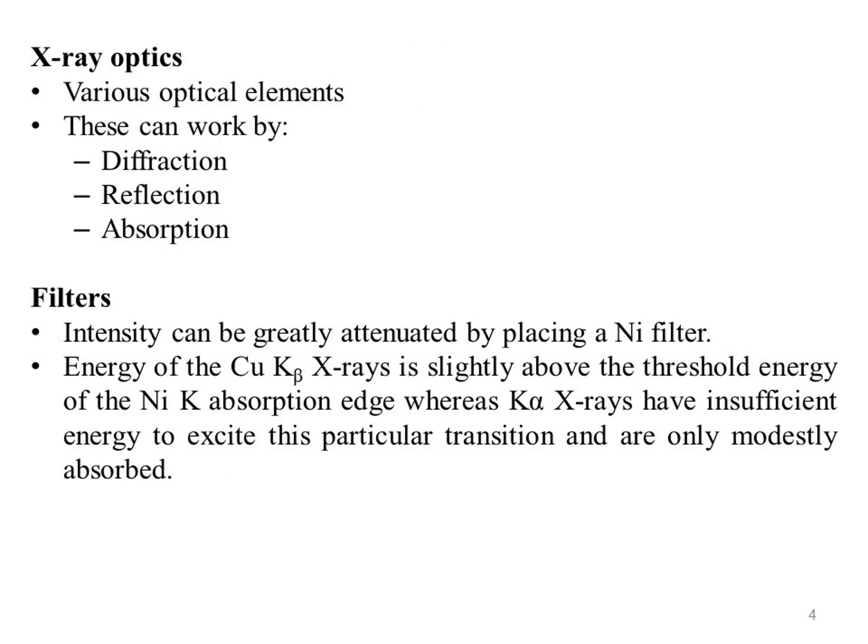Now we will discuss what X-ray optics are. Various optical elements can be placed in the beam path to tailor the characteristics of the X-ray beam. These can work by diffraction, for example, a monochromator crystal, reflection like a mirror, or absorption like a filter or slits.